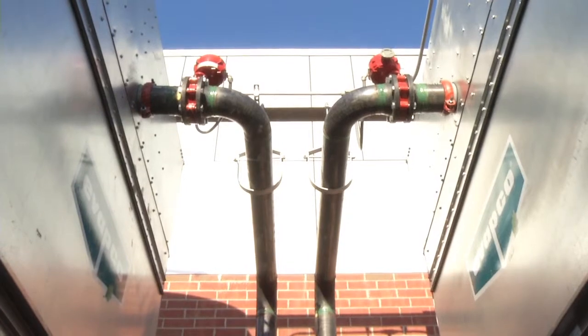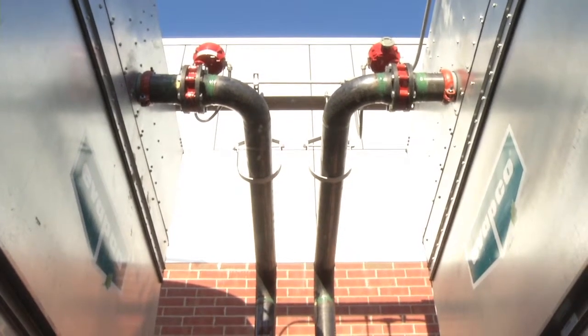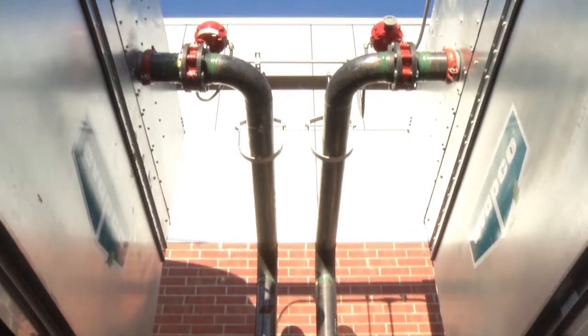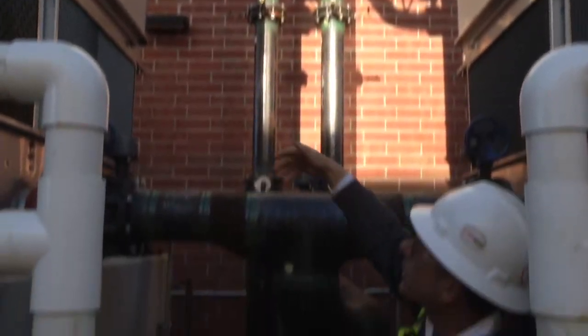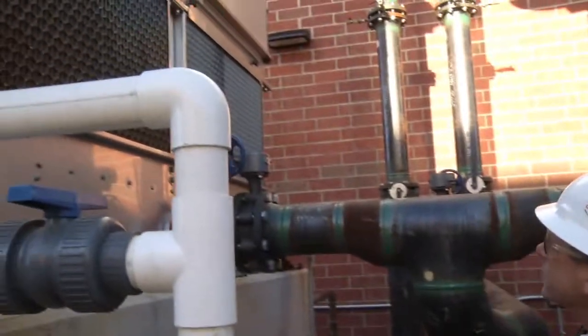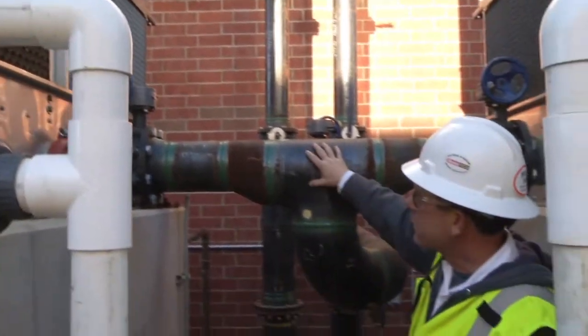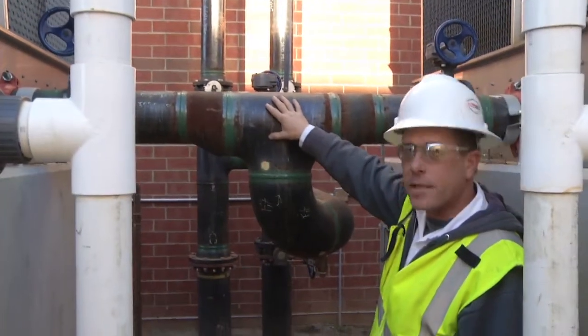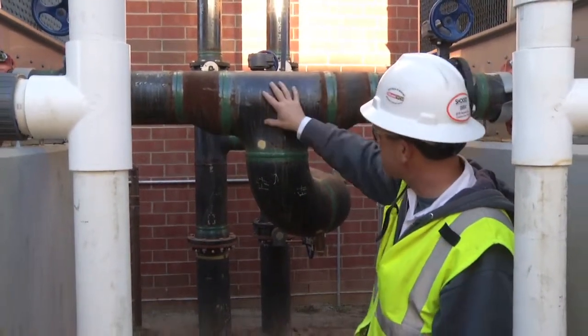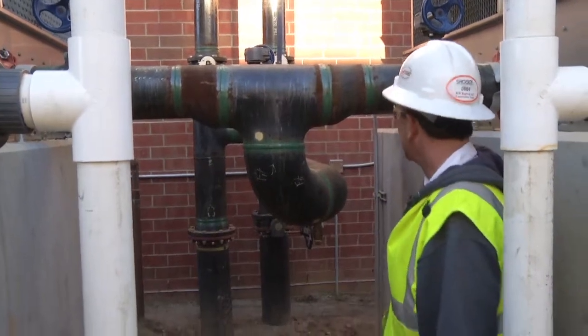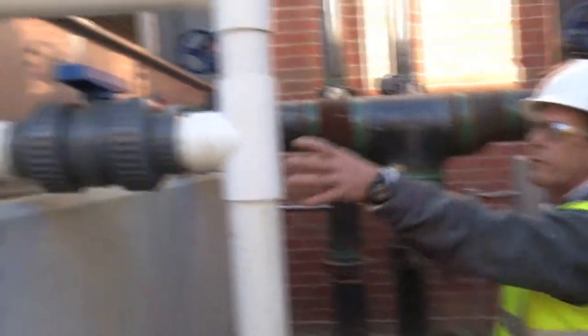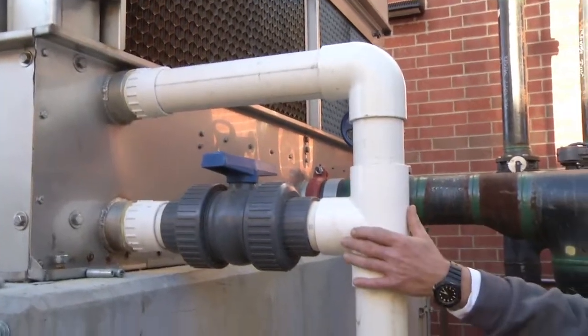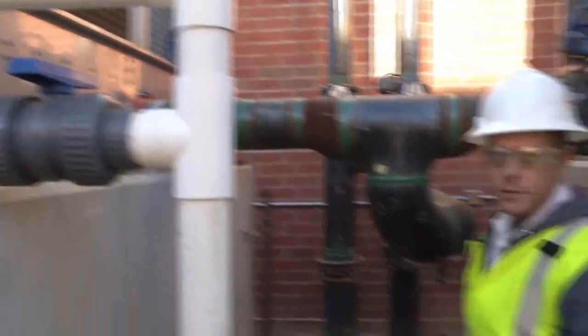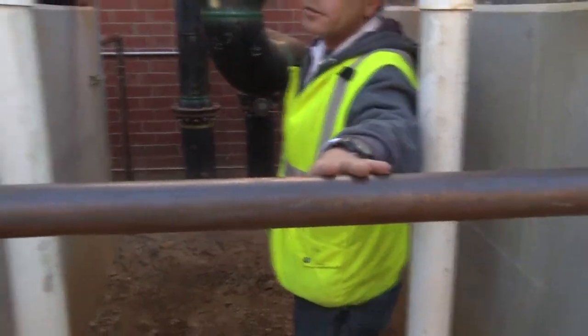All right, these two top pipes are your supply pipe into each cell, cooling tower cell. Goes in the top, actually flows down where air comes in the side and is taken out the top. This is the return piping right here from the bottom of the basin on both towers. This is the equalizer line hooked together. It goes out. This is your overflow piping right here, and this is also your drain piping. This copper line right here going to each cell goes to the mechanical float in each one of the towers.